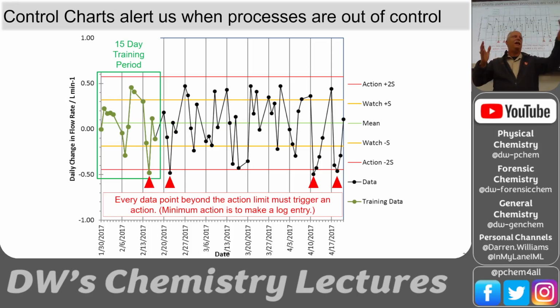We're going to have 15 days of data, and that is a training of our understanding of the process. We're kind of training our expectations, okay? So we want to find out what the mean of the data is and what the standard deviation is. Over 15 days, that's a population of data points, so we should have a good feel for how the process behaves after 15 days. And then we lock that mean in, and we lock that standard deviation in, and we don't calculate it anymore.